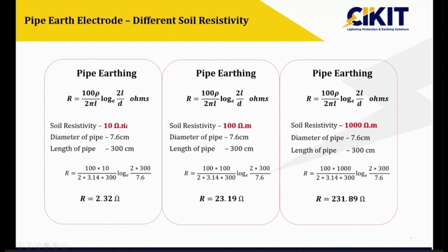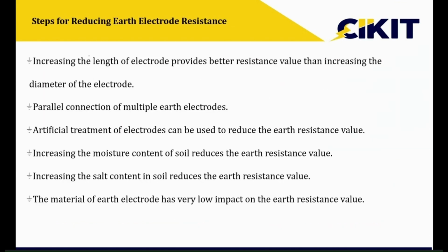So here you can see in all the three cases, the diameter of the pipe, material of the pipe, length of the pipe, all are same. But we are getting three different values and there is a huge difference between these values also. The main reason is the soil resistivity. So if the soil resistivity changes, earth resistance also will change. It is not at all possible to achieve the particular lower resistance value in all types of soils.